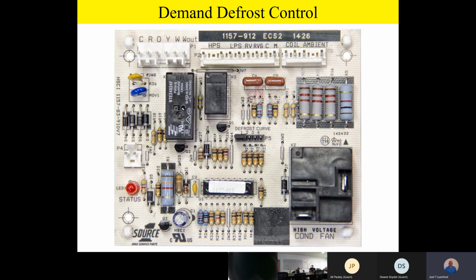ambient. A demand defrost control is always going to have a coil temperature sensor. It's also going to have an ambient or outdoor air temperature sensor. Now, what happens on the demand defrost control is that it's constantly comparing the outdoor air temperature with the ambient sensor and the coil temperature with the coil sensor.